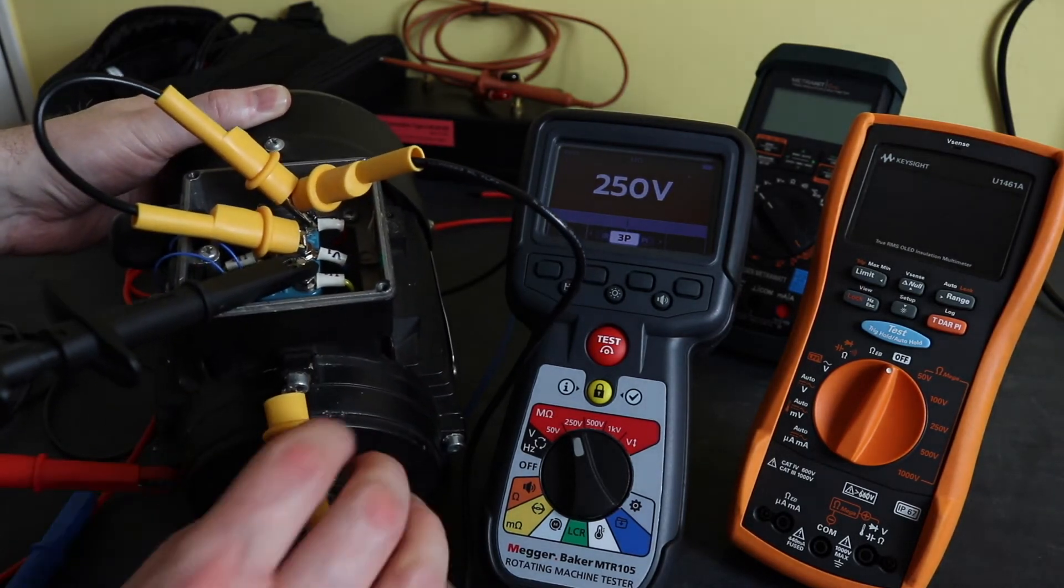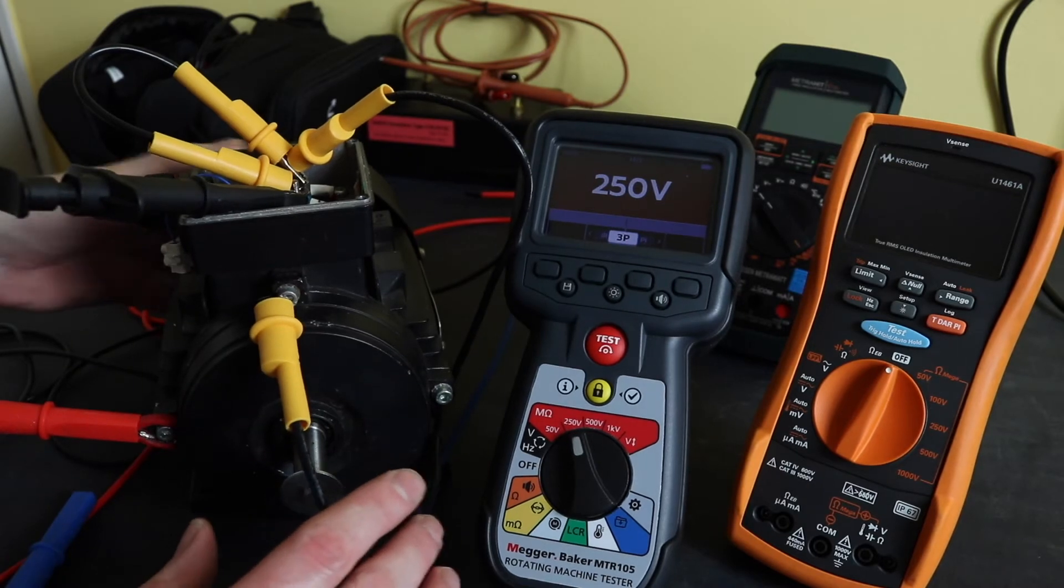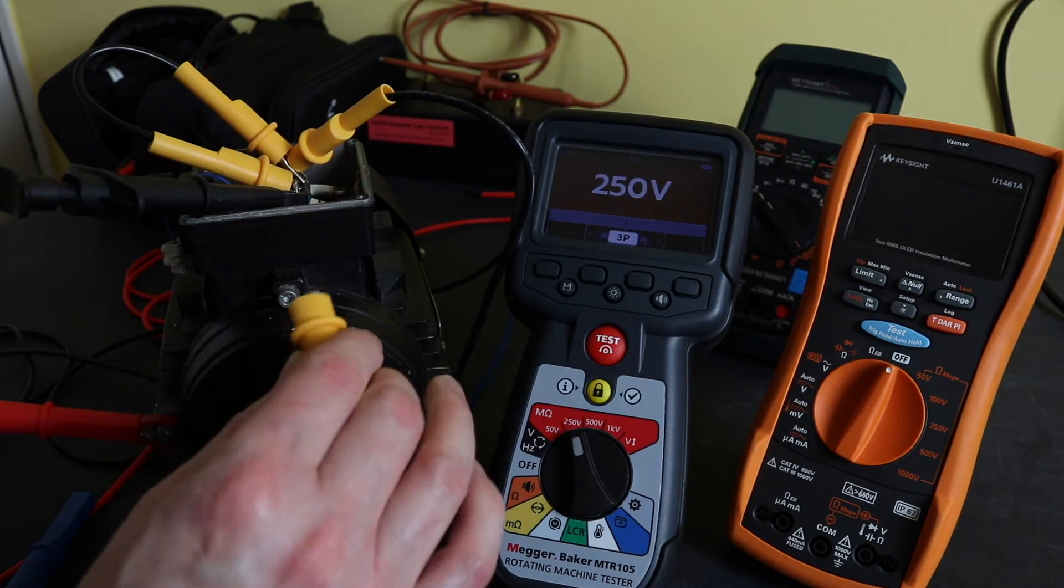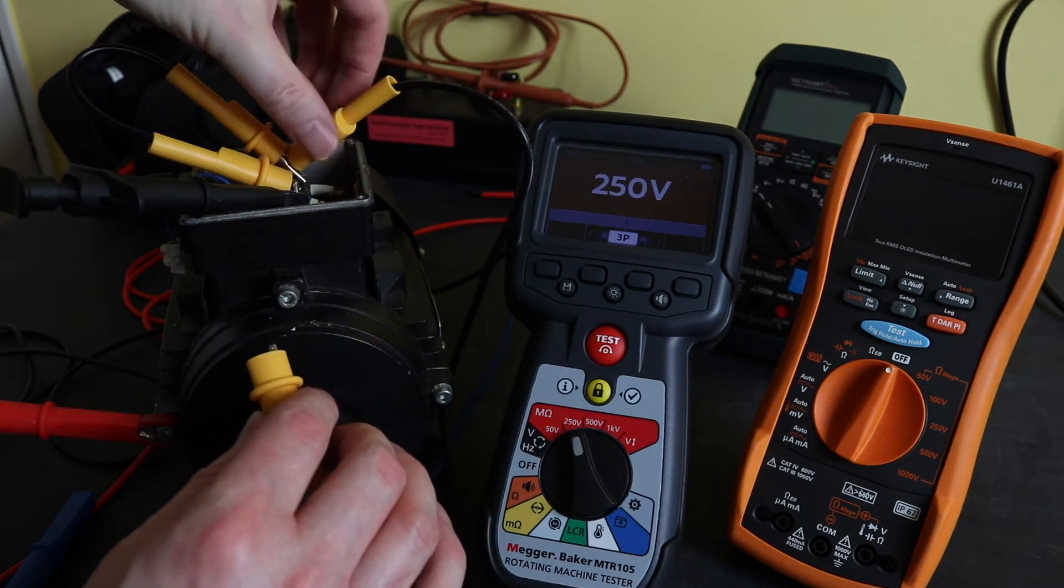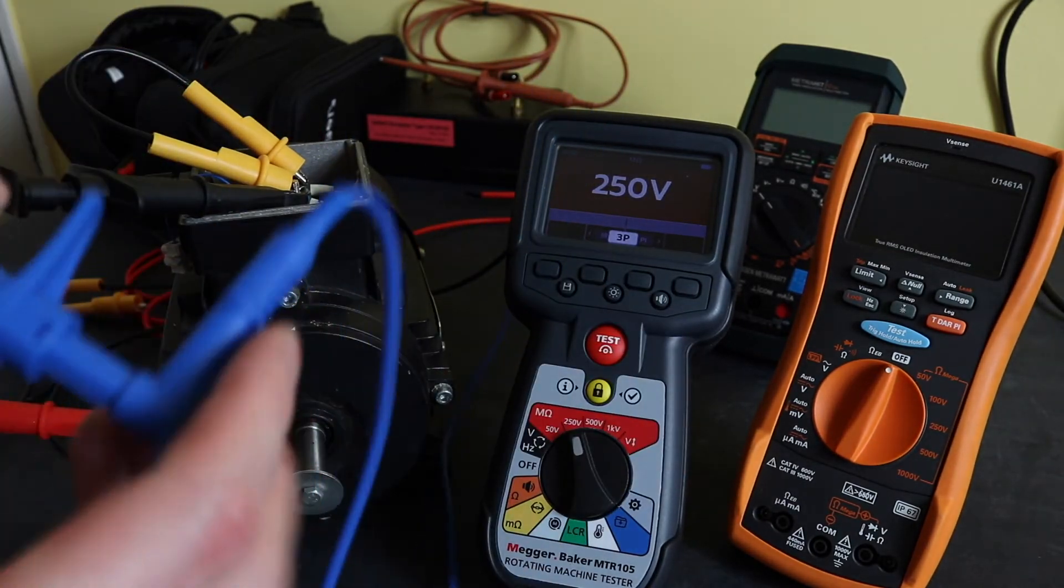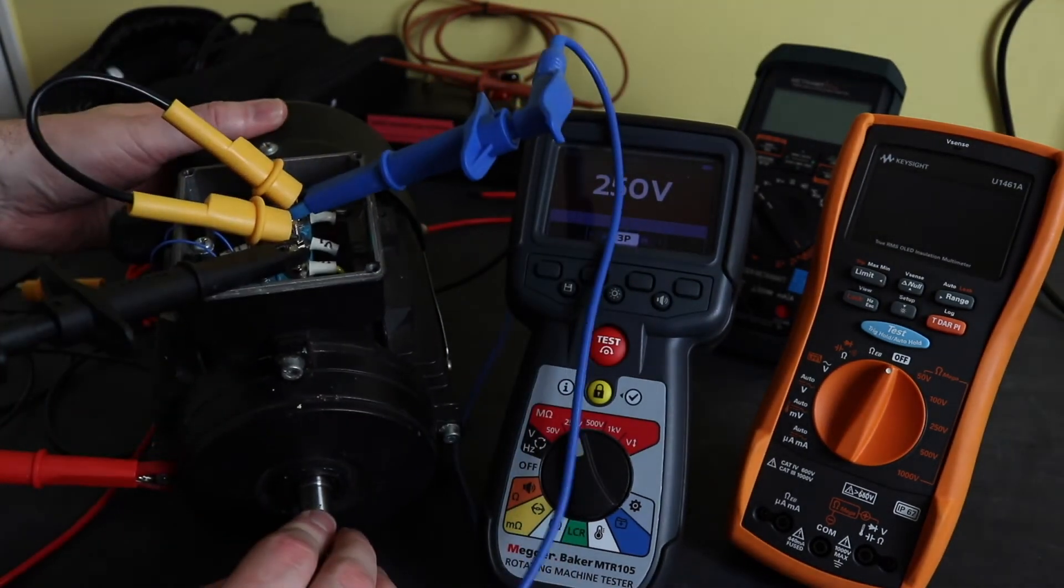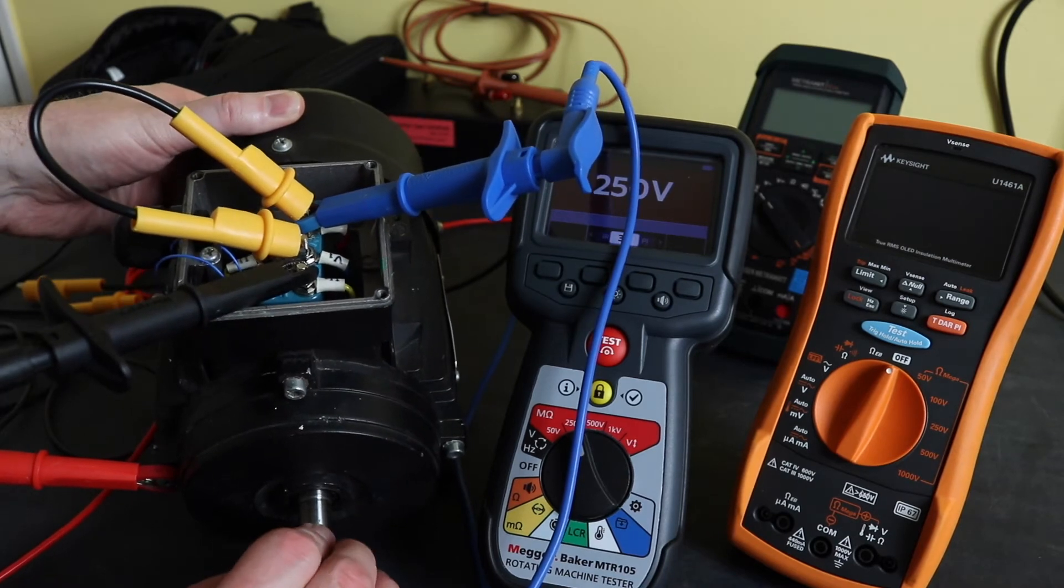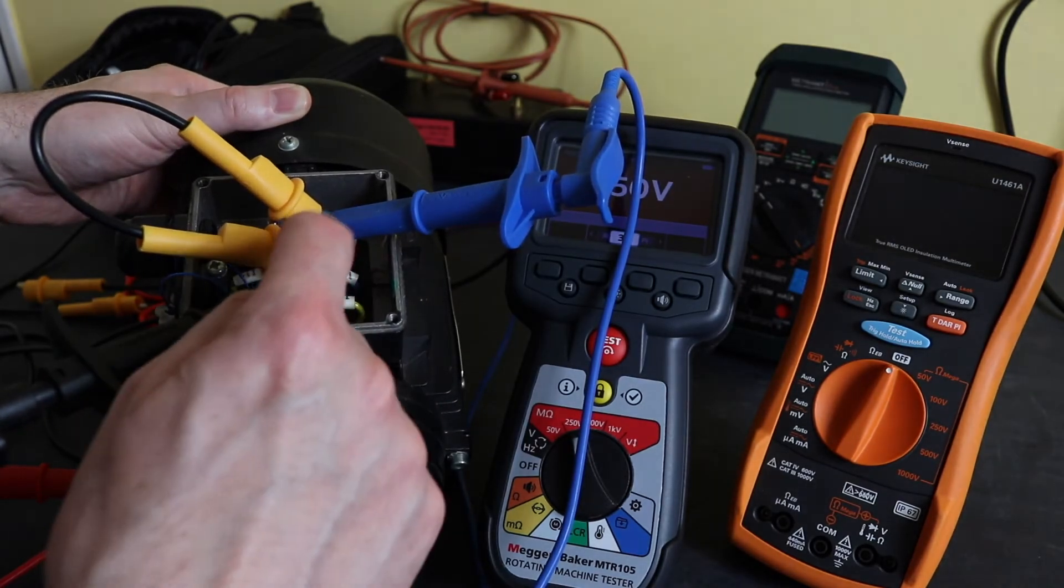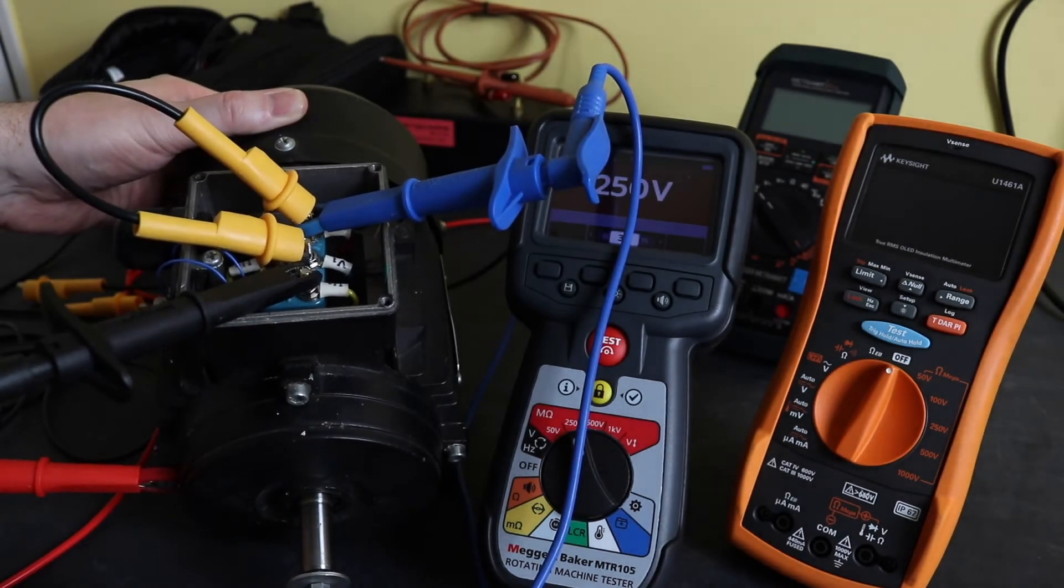A slight alternative to that would be to use the guard terminal, which this MTR-105 has, and has actually another unique feature of it. So to use that, I would remove this link that takes the two windings to Earth, and I would connect the guard terminal onto the two windings that are not under direct test. And that way, I would then get a true reading of this winding just to Earth, as any leakage into the other two windings will be taken away via this guard terminal on the insulation tester.